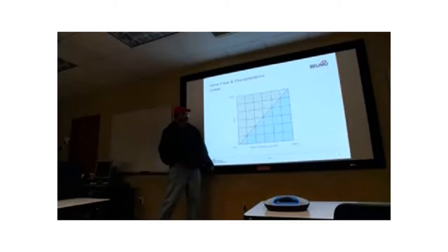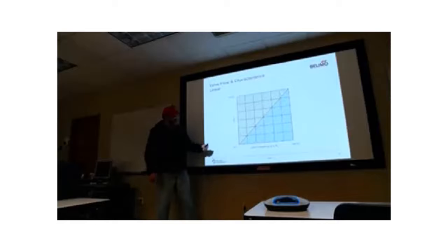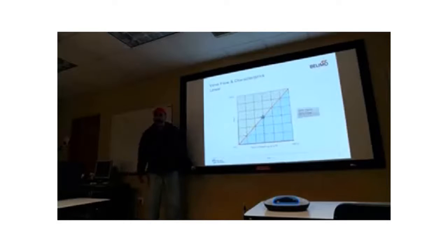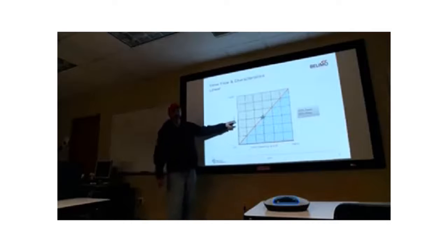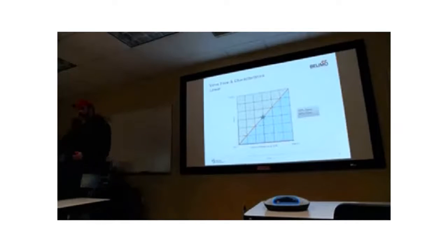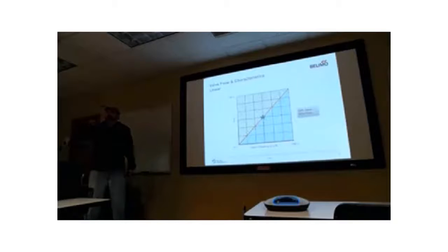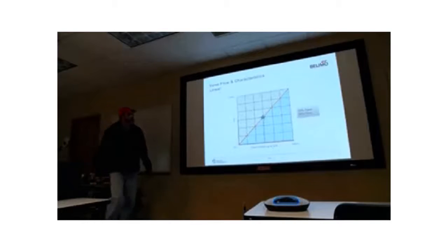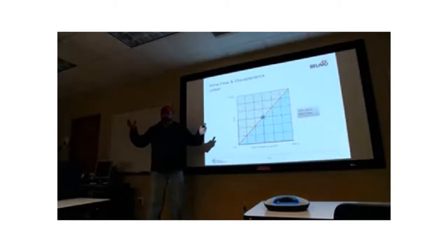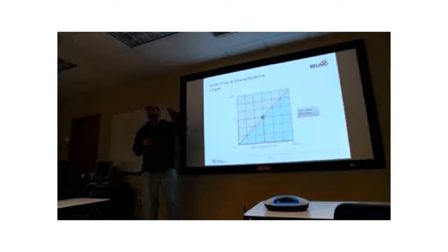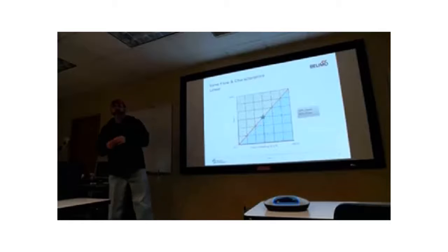Here's the second one, and these are major types: linear. So linear means that the relationship between the opening of the valve and the flow through the valve, in percent, is basically 1-to-1, right? So you open the valve half open, you get about half the flow through the valve. So what kind of application do you think that would work for? Modulating. Or modulating. Sort of, yeah. So I know where you're going, and this is one of the reasons we did this. Think about the applications, like for water. What kind of valve would you want where if you open the valve half open, you want half the flow of the water through it? Or a coil or hot water valve. I'm going to say no, but I'm going to explain that in about 5 minutes.